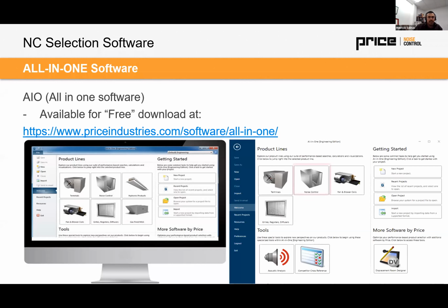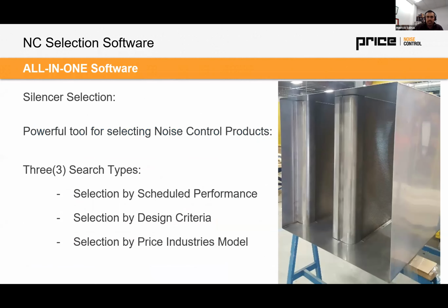Okay, all right. So now there are three ways to select silencers in the software, and I'm going to show you in the demo here. One is going to be by scheduled performance. One's going to be by design criteria, meaning you have a fan and then you have sound power levels and you want a quick selection of a silencer to get you a certain dBA level or NC, whatever the weighting method specified by an acoustician, building owner, or your jurisdiction.